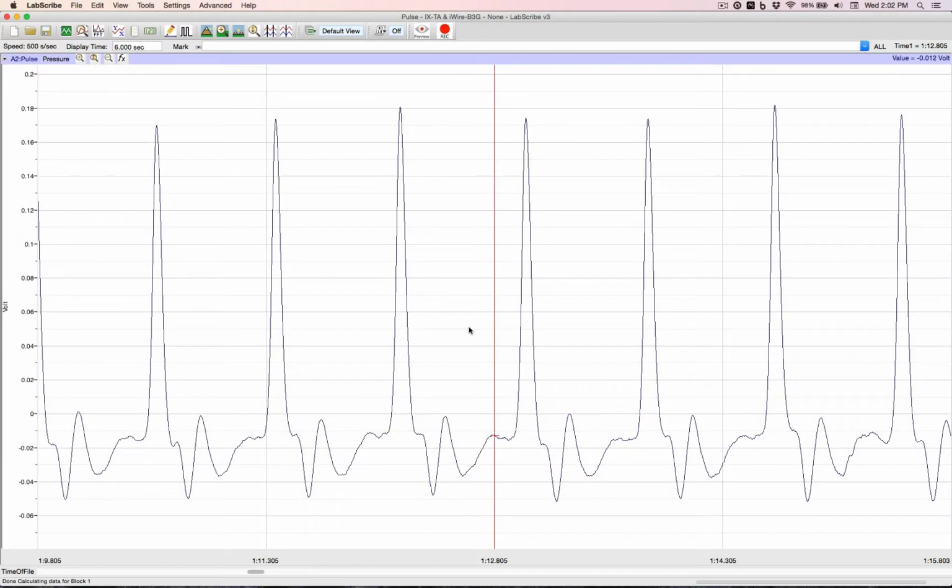In this tutorial, let's talk about units conversion. If you're using an iWorx TA, then most of the common sensors are already pre-calibrated, so you won't have to go through this exercise. Otherwise, you'll have to do a two-point calibration. All probes read volts. So what we need to do is find two reference points of known value, and we can do a two-point calibration.